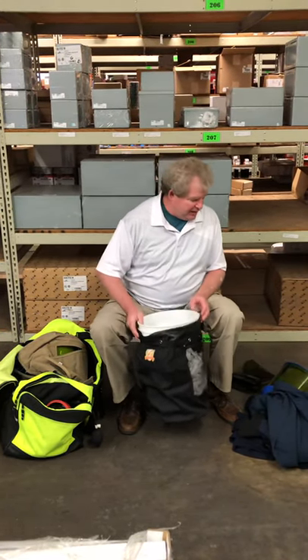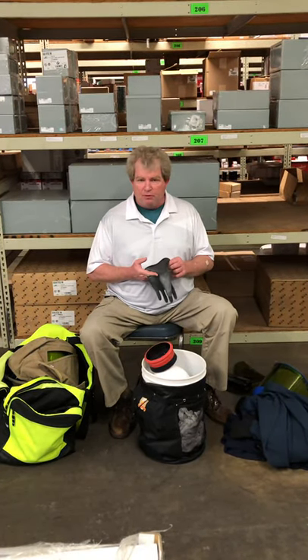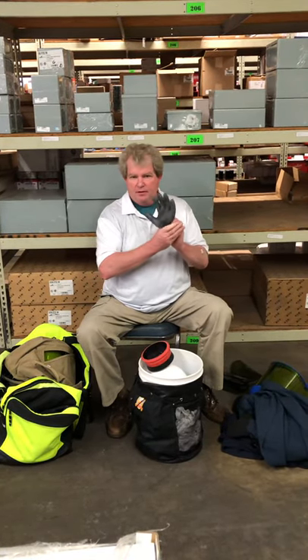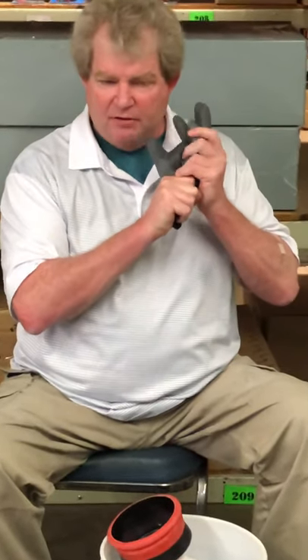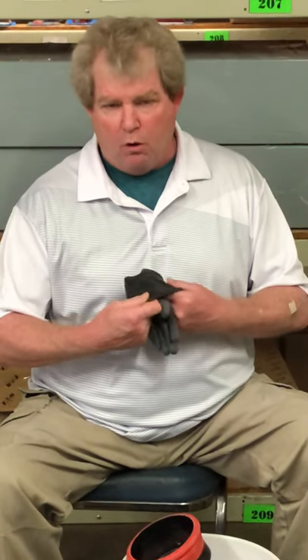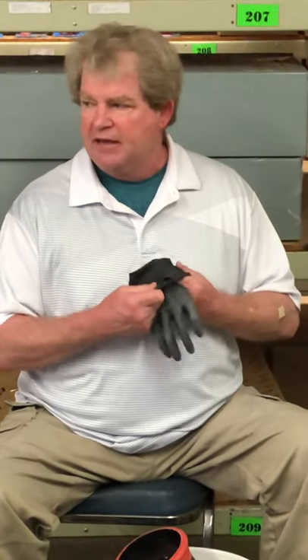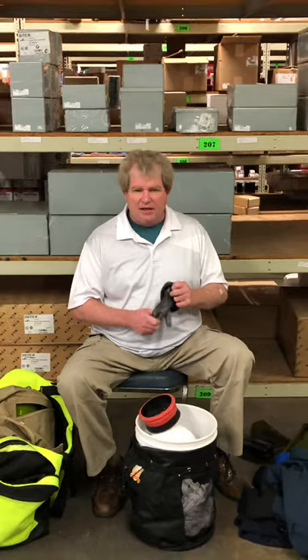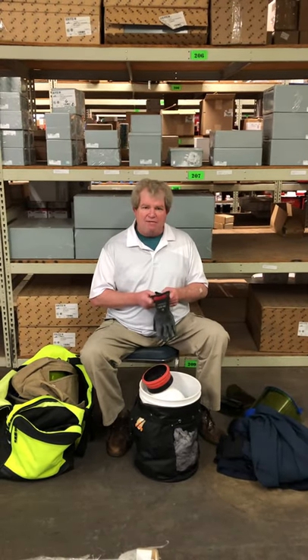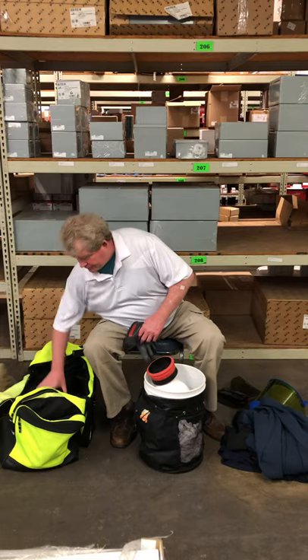The third area of protection is rubber gloves. Rubber gloves have to be tested for puncture before every use. Most people do something like this — you get a quick air test, but you're only doing half the glove. For the other half, invert that glove and do what's called blow and roll — invert and stress, put some stress on it. We were out in Michigan doing this and when the guy got to that point, his glove tore right there. He had a pinhole in his glove. Pinholes make the glove absolutely worthless — we're wearing this glove for shock protection, it's got to protect us from shock.